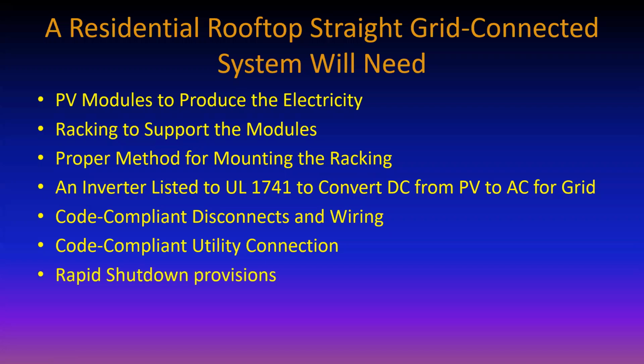Rapid shutdown provisions, and that's what we were talking about as far as fire protection. From ground level, you need to be able to shut down every ounce of electricity that's coming out of that array, except for the modules themselves and within a couple of feet of each module. But otherwise, the rest of the building goes down if you shut down the main disconnect of the building. That then shuts everything else down.